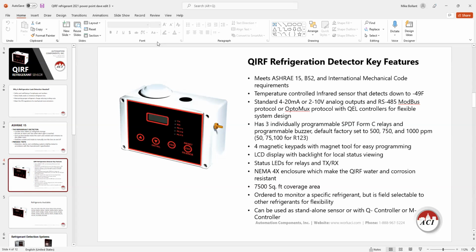We've got all the Freons downloaded into the microprocessor. If you have any questions on that, you can call in here and we can walk through it with you in about 5 minutes. It also comes with a 4 to 20 or 2 to 10 analog output besides the RS-485. It can go down to minus 49 degrees F. A lot of times you're going to see specs where you might have 2 chillers in a room and they're both the same Freon. Depending on the same mechanical room, you don't really need 2 sensors. You just put one in between and it covers 7,500 square feet. So you're covered. You don't need 2.